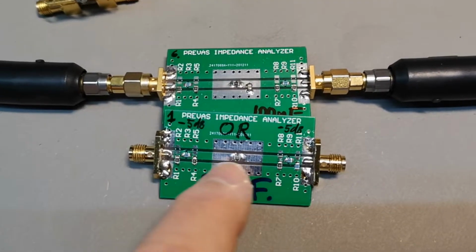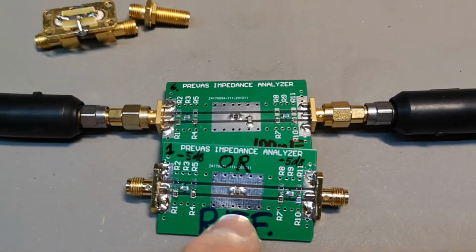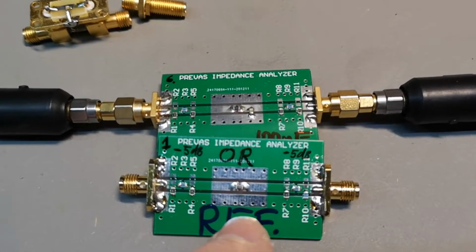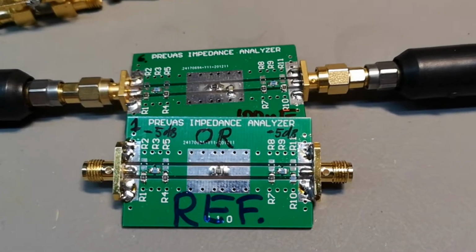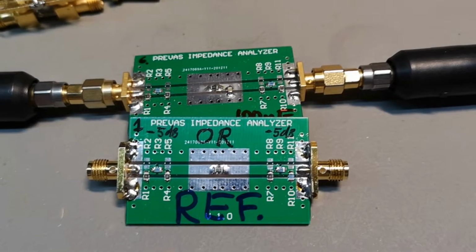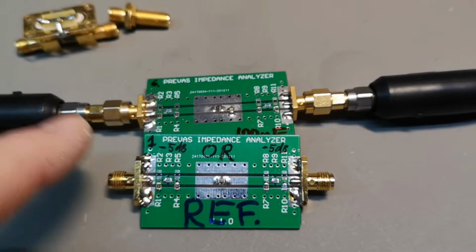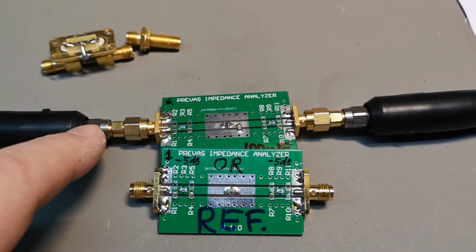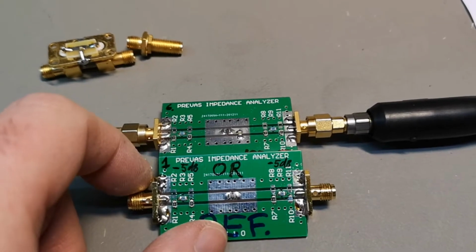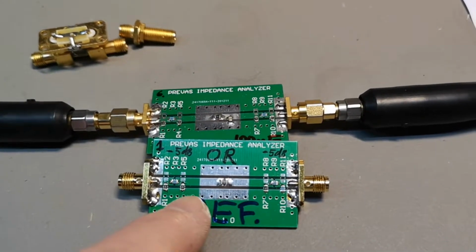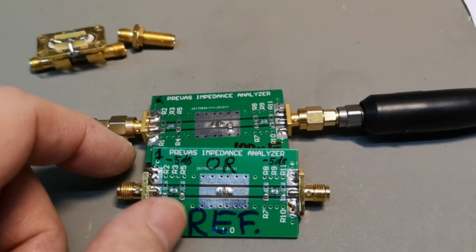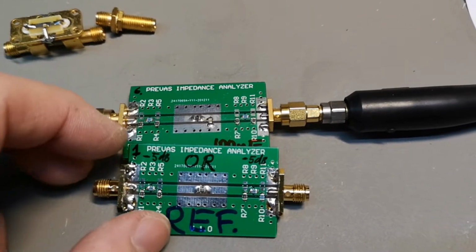This means that the test object will be tested at a resistive impedance that is not affected by cable resonance or length of the cables, so that the curve will get a lot less ripple and will not be affected by the cables or the analyzer.